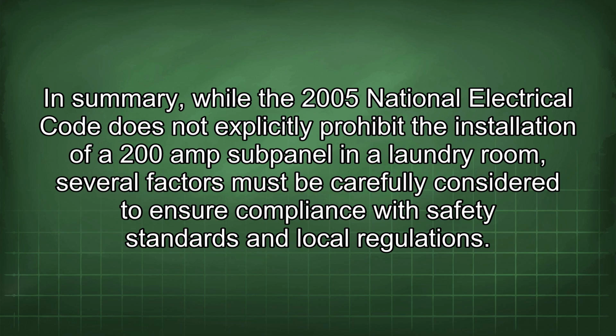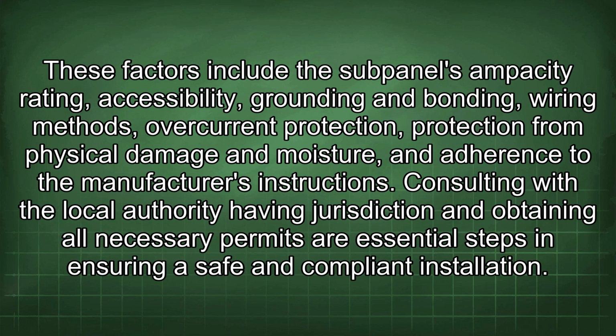200 amp subpanel in a laundry room, several factors must be carefully considered to ensure compliance with safety standards and local regulations. These factors include the subpanel's ampacity rating, accessibility, grounding and bonding, wiring methods, overcurrent protection, protection from physical damage and moisture, and adherence to the manufacturer's instructions.